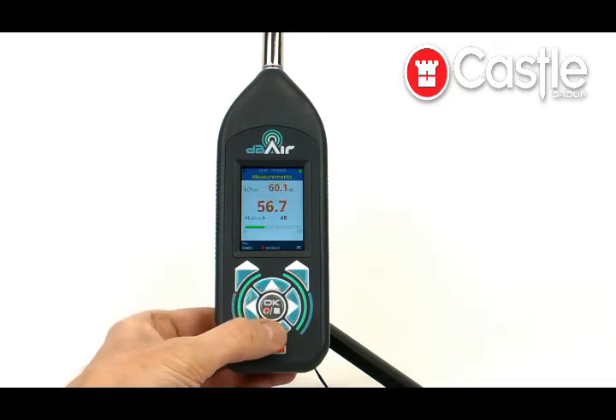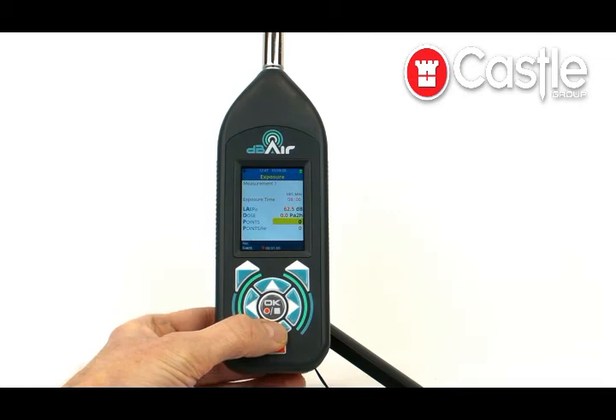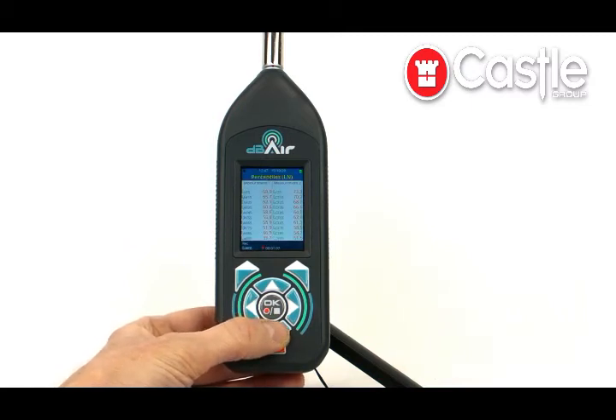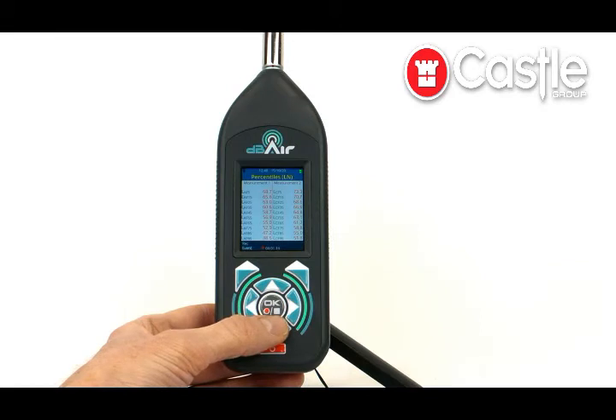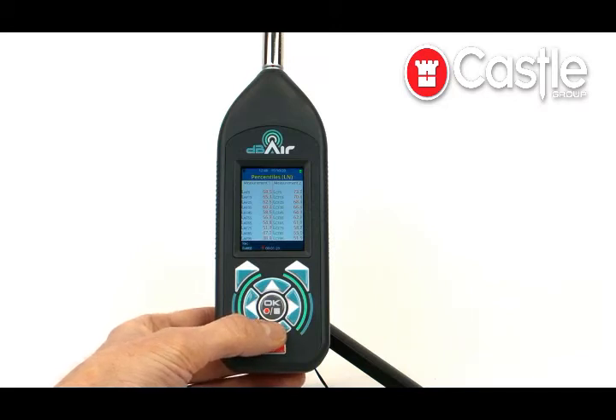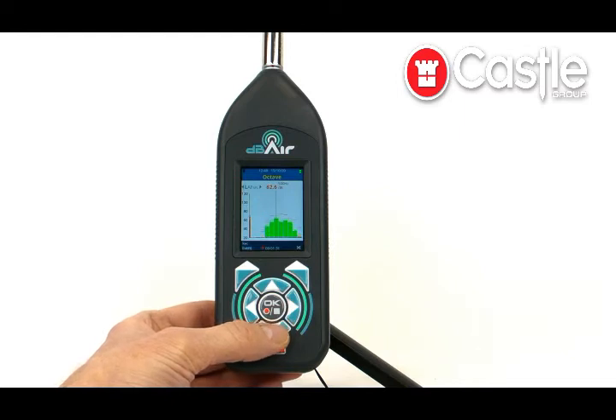Pressing the downward arrow key takes you to different measurement screens. There's a screen showing all the measurements together in one table, then a screen showing exposure calculations — calculated exposure results based on the LEQ. We then have percentile values for measurement one and measurement two displayed together. Finally, this is set to measure single octave bands, though the meter is also capable of breaking that down into third octave bands.